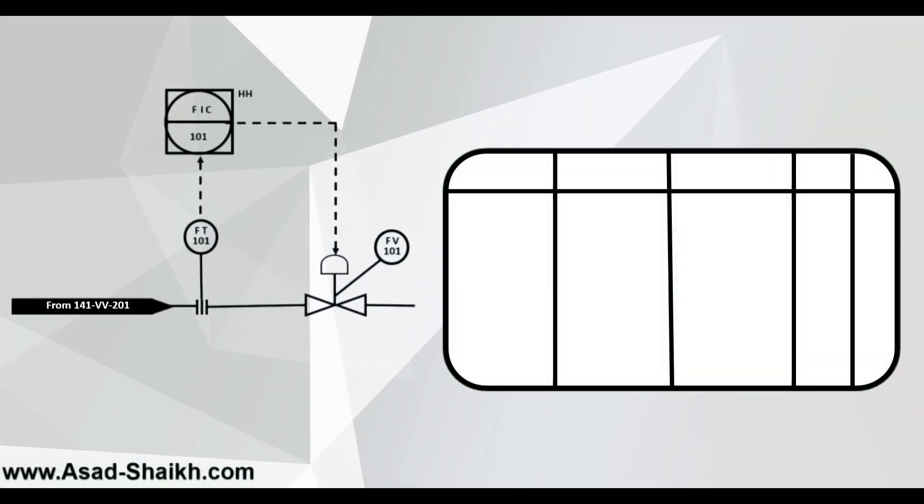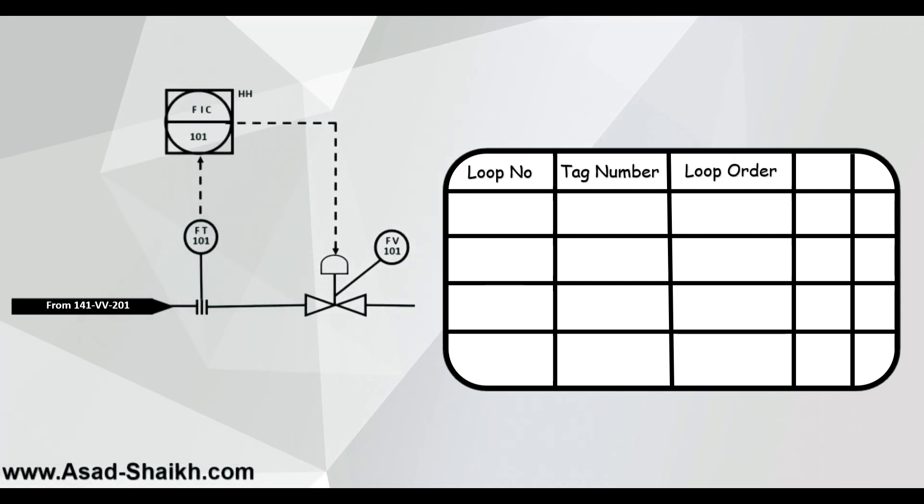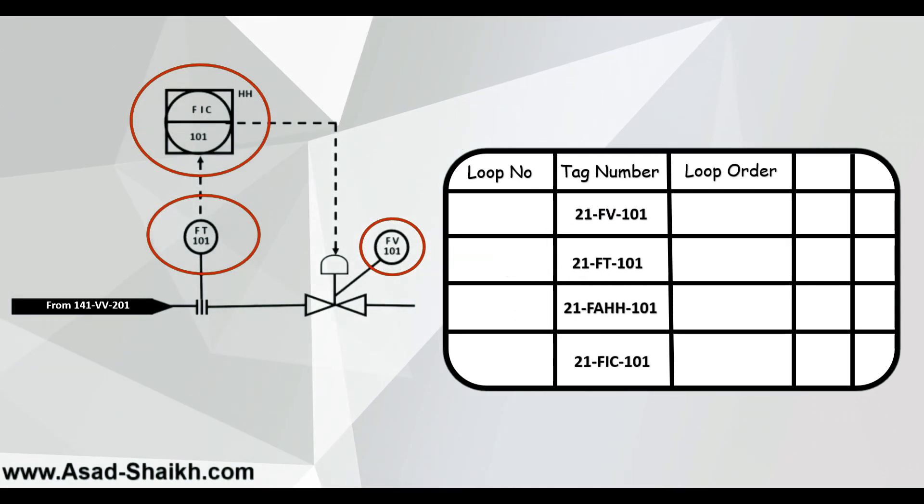Try to plot instrumentation index by seeing the three most important parameters first. You might agree that loop number and tag number are important but you might think what is so useful in loop order. So before that if you see these three are basically the tags but there's another fourth one. You see that HH written here near the controller that stands for the high high alarm. So even that has to generally be documented in an index to know what are the alarms that are available.